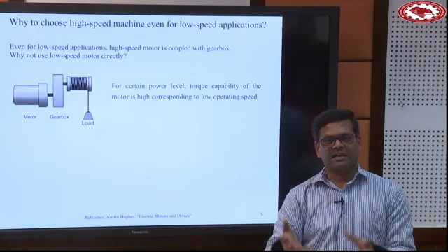The second advantage is, when I say high torque machine, the current is high. Therefore, the heat produced by the machine is proportional to I square, right? So more heat is produced. A high torque machine, 100 RPM means high torque, because we have fixed the same power, 20 kilowatt, right? Because 4 people have to be carried. So in one case, 100 RPM, it carries high current, and I square multiplied by time corresponds to the heat energy. In another case, there is less current, so the heat produced is less. So heat produced is more, heat produced is less. The ohmic loss in the conductor, in the winding, is more in a high torque machine, therefore the efficiency of the system is less, right?